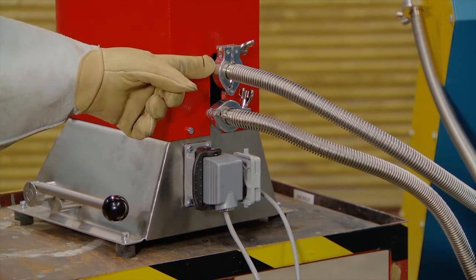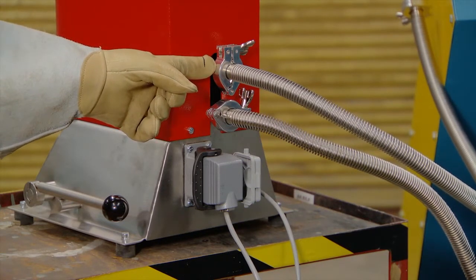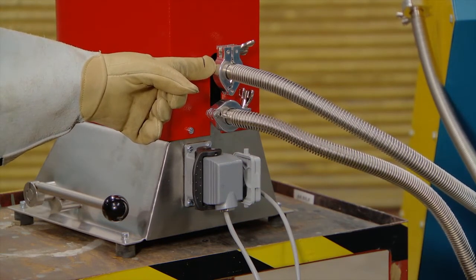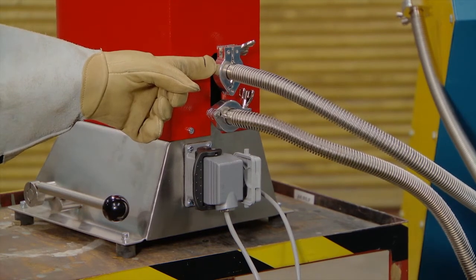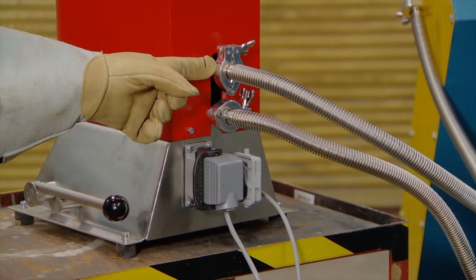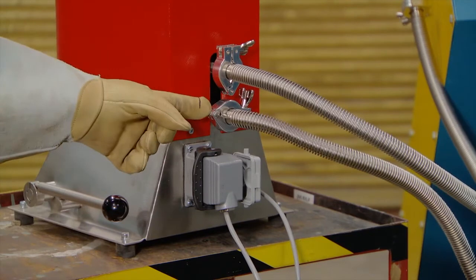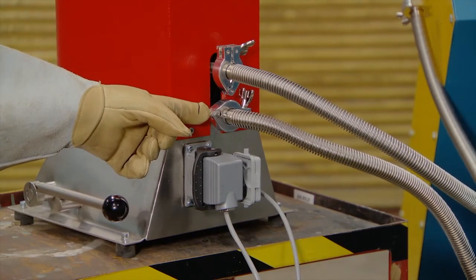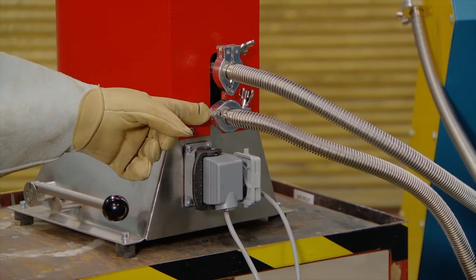The upper vacuum connection should be connected to a point between the Roots pump and the transformer, that is on the low pressure side of the vacuum pump. The lower vacuum connection should be connected between the Roots pump and the vacuum pumps, that is on the pressure side of the Roots pump.